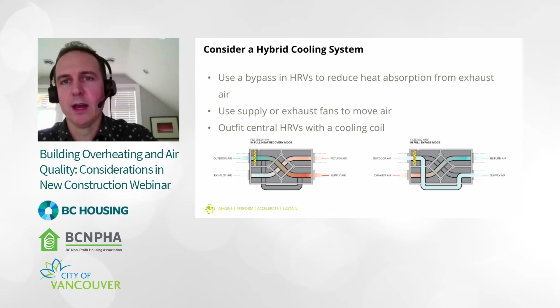Also, the ability to actually increase the airflow, the outdoor airflow, can be very effective. We're using fans, so it's technically an active system, but increasing the capacity to bring in more of that cooler outdoor air when it's useful is something to consider. So it may mean increasing the capacity of the unit slightly, and increasing the size of ductwork, but understanding the impact that can have on mitigating overheating, and comparing that against the capital cost investment is one way of leveraging what equipment we have, and can be very cost effective.